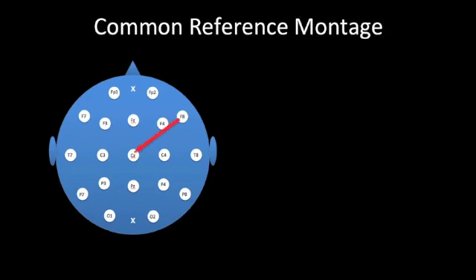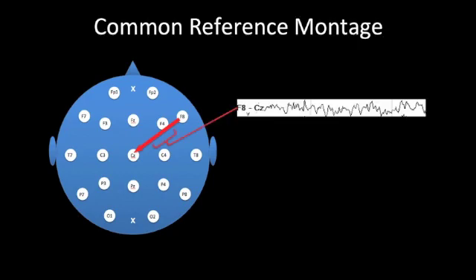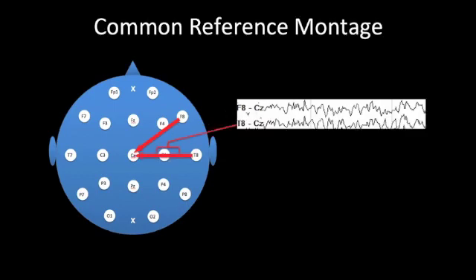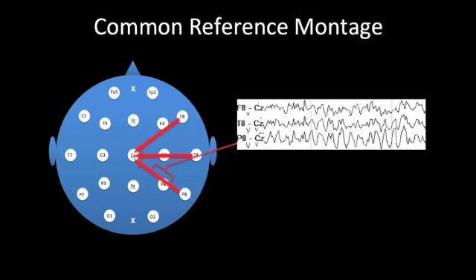The second type of montage we will discuss is the common reference montage. In this situation, we compare the signal at every electrode position on the head to a single common reference. One of the most common is the Cz montage, where we compare every electrode on the head to Cz. For example, the first channel is F8 to Cz, then moving posteriorly, T8 to Cz, and then P8 to Cz, generating a chain in the same way as the anterior-posterior bipolar montage.